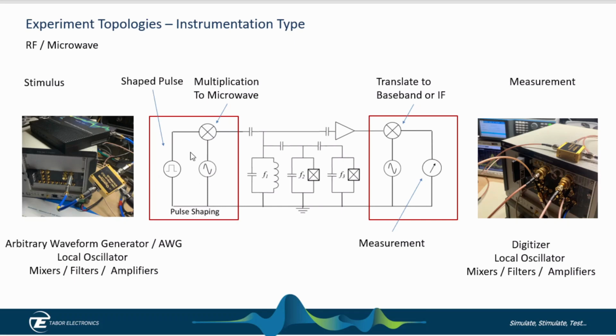We need to upconvert that essentially, so we have a local oscillator. That would be a signal generator. So I have our Lucid signal generator here, providing the local oscillator to the microwave mixer here. Then we're either going to do 4 or 8 gigahertz stimulus to this, and then we're going to measure it. So we're going to down convert it.